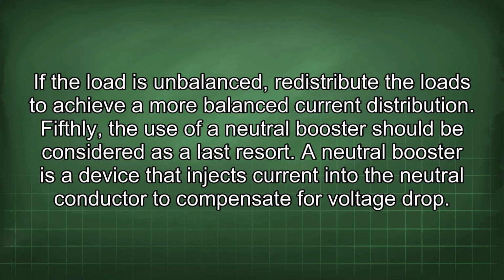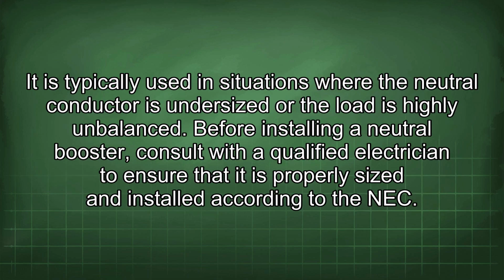Fifthly, the use of a neutral booster should be considered as a last resort. A neutral booster is a device that injects current into the neutral conductor to compensate for voltage drop. It is typically used in situations where the neutral conductor is undersized or the load is highly unbalanced.